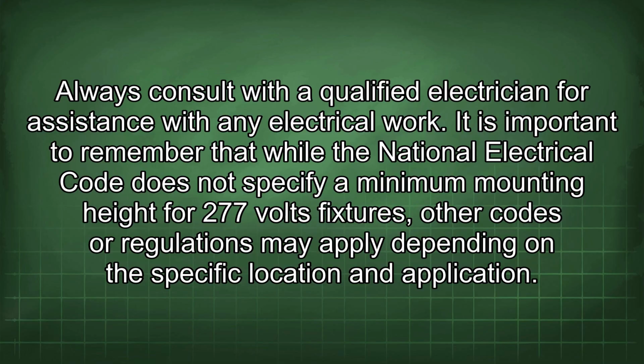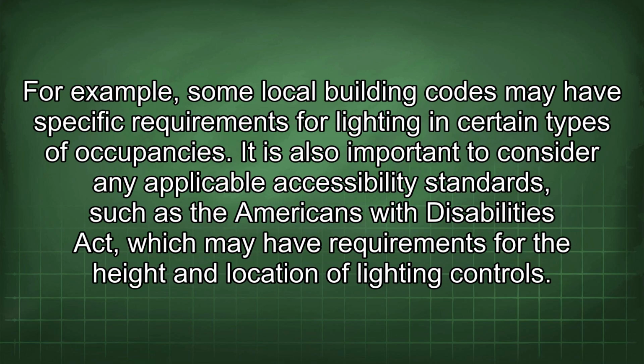It is important to remember that while the National Electrical Code does not specify a minimum mounting height for 277 volts fixtures, other codes or regulations may apply depending on the specific location and application. For example, some local building codes may have specific requirements for lighting in certain types of occupancies. It is also important to consider any applicable accessibility standards, such as the Americans with Disabilities Act, which may have requirements for the height and location of lighting controls.